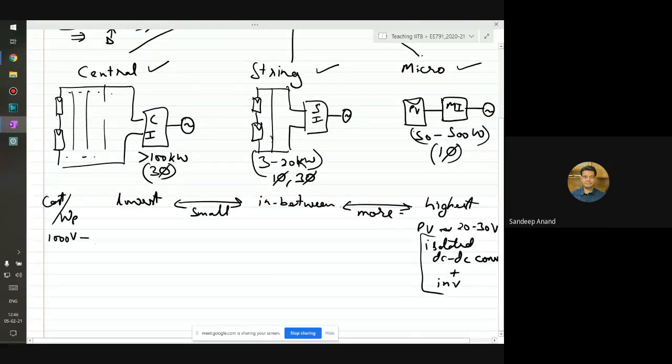And if it's a three-phase voltage source converter, what will be the maximum DC voltage if the grid is 400 volt? It will be the peak of the line-to-line voltage, and a little bit more than that, so it might be around, let's say, 650 or something. So ideally you would expect the DC link voltage to vary between 1000 and 650.